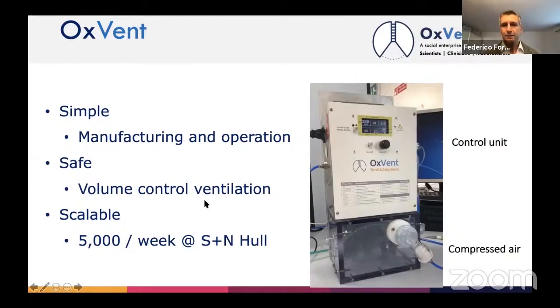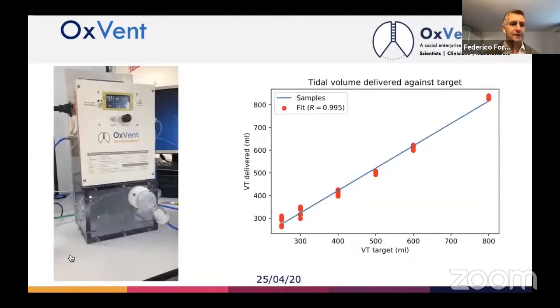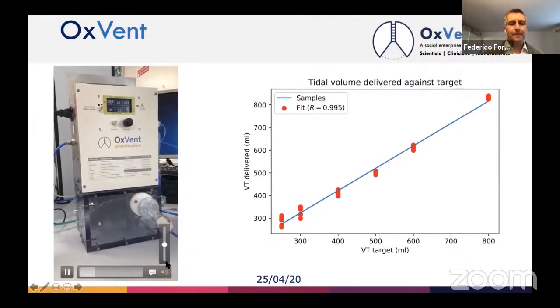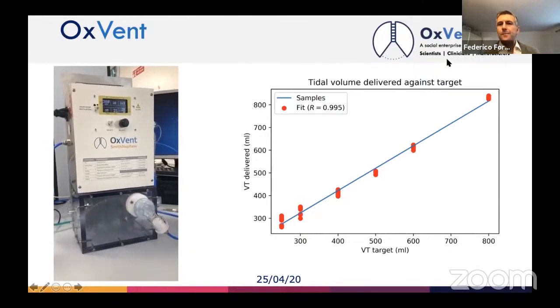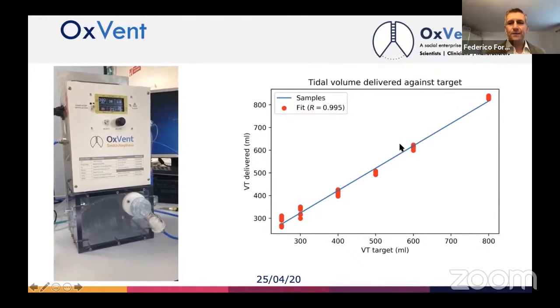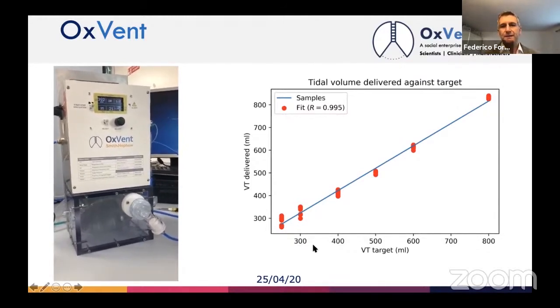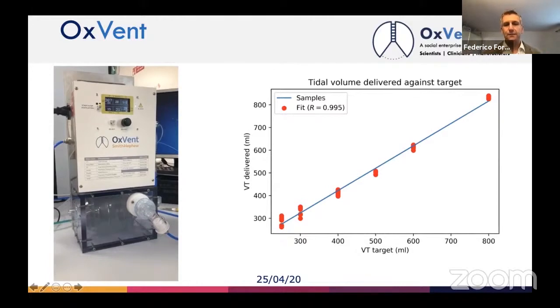This is just an image of the ventilator. And here we see it a little bit in action on the left. I'll just reduce the volume. You can only hear the noise it makes. And on the right, we see results from bench testing. I'm not going to go into much detail here, but we had a target volume of air that we wanted the ventilator to deliver to the patient. And what was measured by a monitoring system independent of the ventilator showed a very linear relationship between the target and delivered volumes.